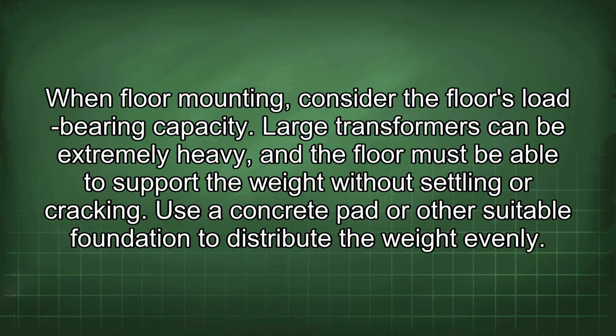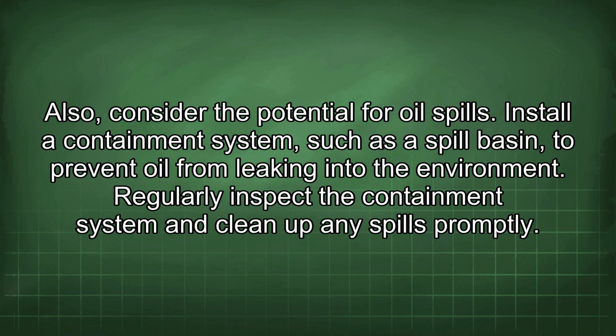When floor mounting, consider the floor's load-bearing capacity. Large transformers can be extremely heavy, and the floor must be able to support the weight without settling or cracking. Use a concrete pad or other suitable foundation to distribute the weight evenly. Also, consider the potential for oil spills. Install a containment system, such as a spill basin, to prevent oil from leaking into the environment. Regularly inspect the containment system and clean up any spills promptly.